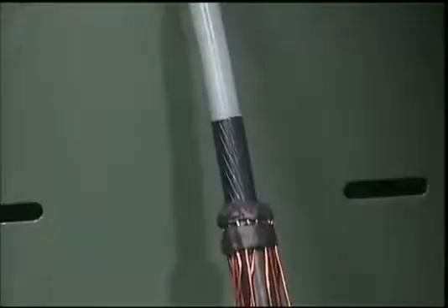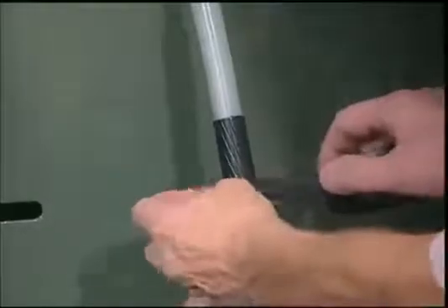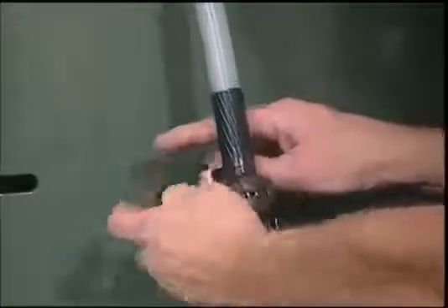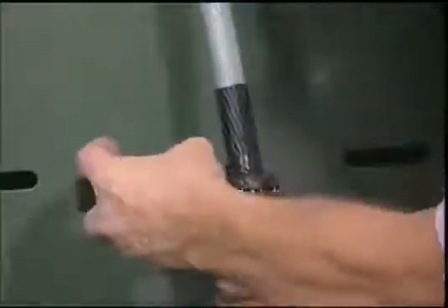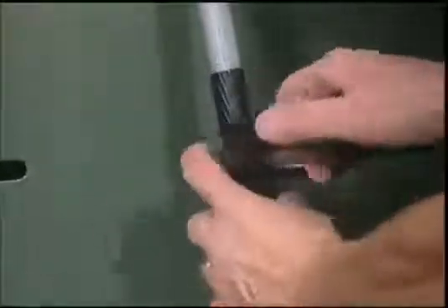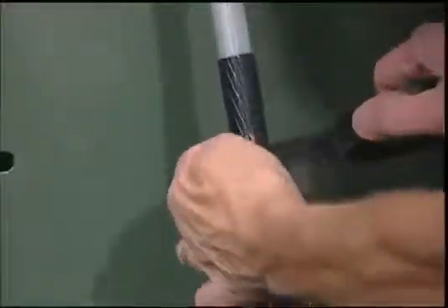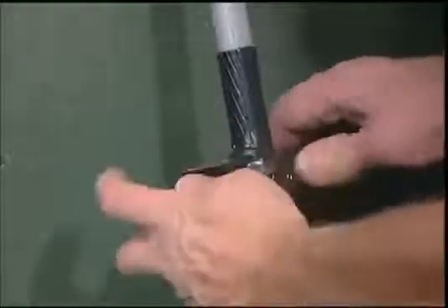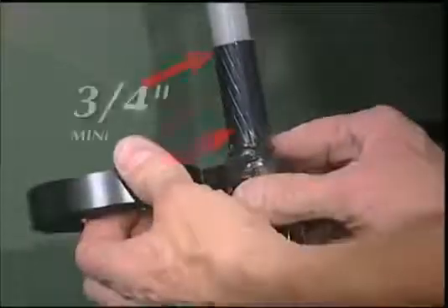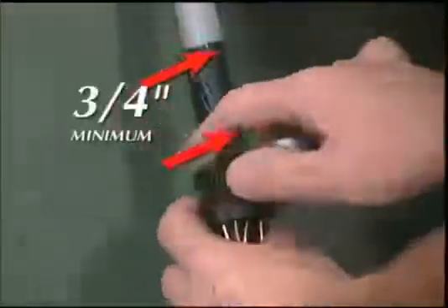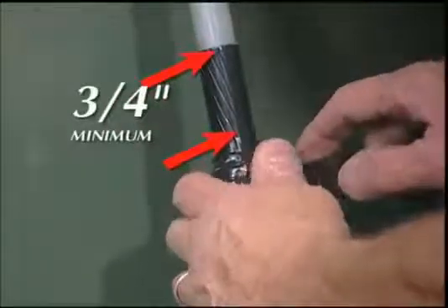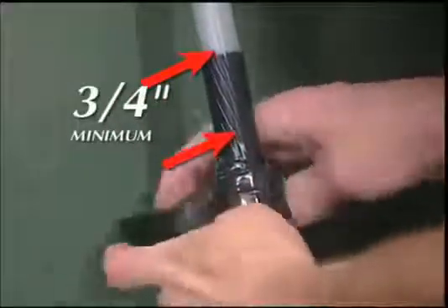Now, wrap the cable and the mastic with a 1/2 lap layer of vinyl electrical tape. The tape should extend from just above the third mastic applied at the transition point to just below the first and second mastic onto a portion of the jacket still in place. Note, a minimum of 3/4 inch of the semiconductor insulation shield should remain uncovered.